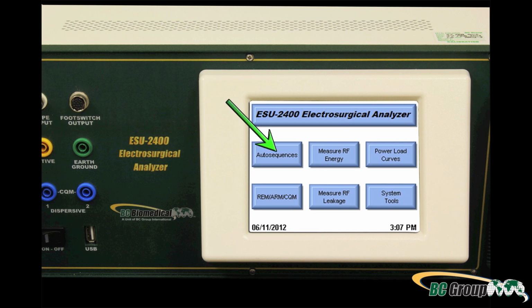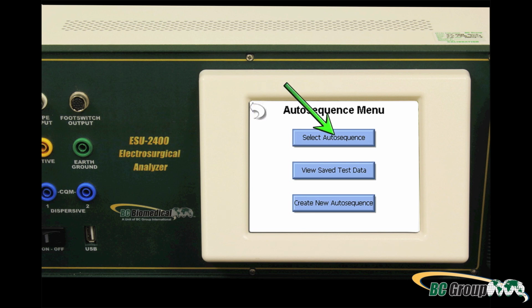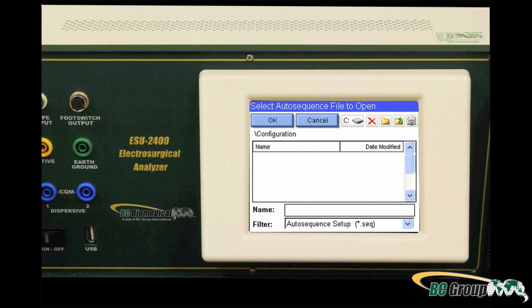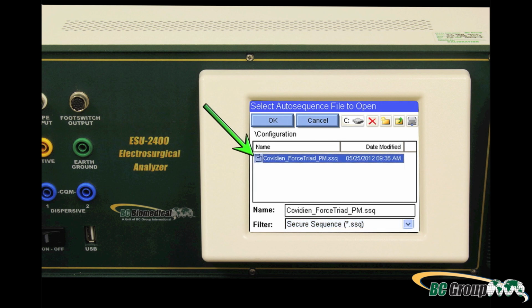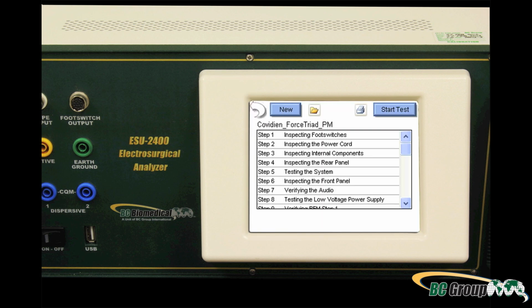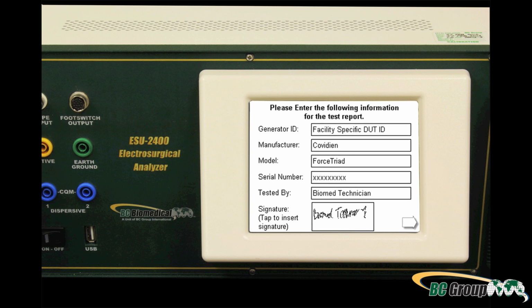Loading the Autosequence. Starting from the ESU-2400 main screen, press Autosequences. From the Autosequence menu, press Select Autosequence. The Open File filter will show Autosequences Setup .seq by default. Change the filter to show Secure Sequence .ssq. Select the file Covidien ForceTriad PM.ssq and press OK. After the sequence is loaded, the screen will display the list of tests that will be performed. Press the Start Test button to begin the PM procedure. You will be prompted to enter information about the device under test. You can enter information by pressing on the text entry box. You can use the on-screen keyboard, USB keyboard, or USB barcode reader to enter information about the device under test. Press the right arrow to begin the test.